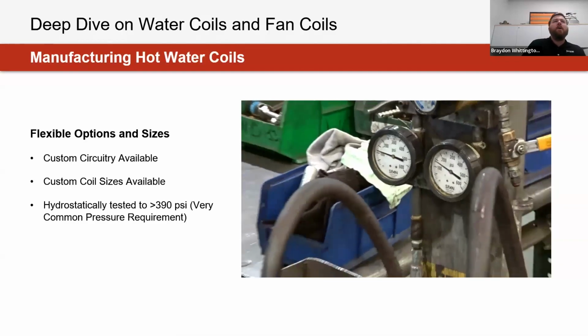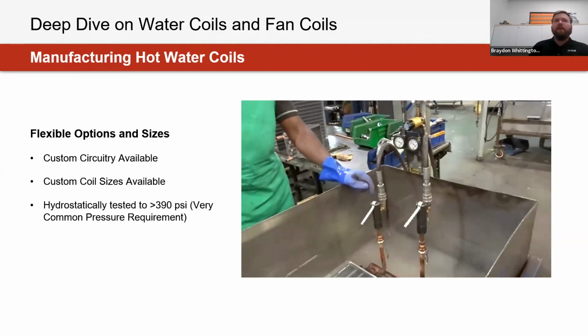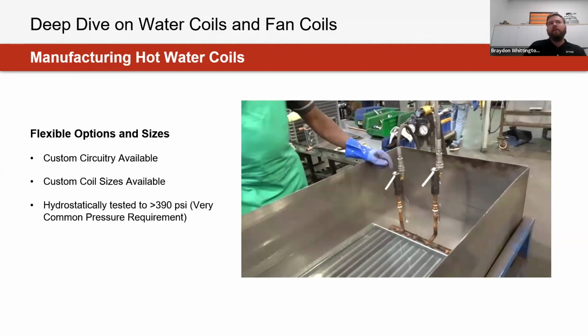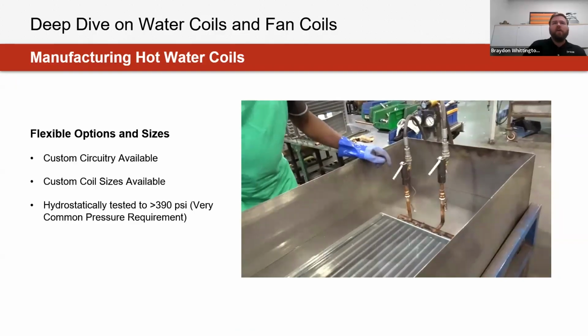Also with these two, very commonly enough, and that kind of ties into having everything in-house, is being able to customize or look at different circuitry that you would see more so once we start looking at fan coil and blower coil equipment and customizing the sizes. But then also, at a specification level, testing all these coils before they're shipped out, to make sure that they've been rated to a certain pressure requirement, just to ensure that we're not going to have any leakage. So it's very common that we're going to see them tested at around 400 psi or above, or that 390 psi requirement, when doing some of the static testing.